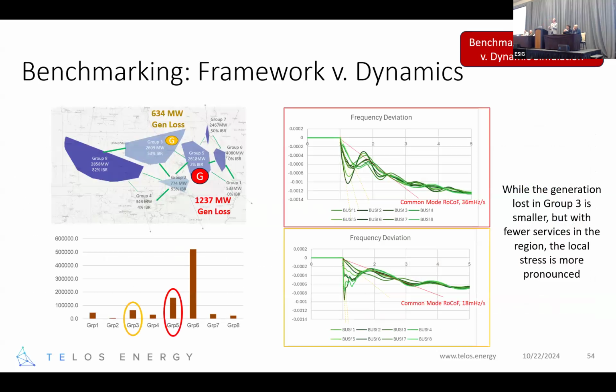Some preliminary results we're seeing — I want to zoom in on a couple of loss of generation events. In this case, we're considering two separate events: a loss of generation, the red generator shown here in group 5, and a loss of generation, smaller but still the largest in the group, in group 3, coded in orange. The red loss is about 1,200 megawatts, and the orange loss is about 600 megawatts, or about half.